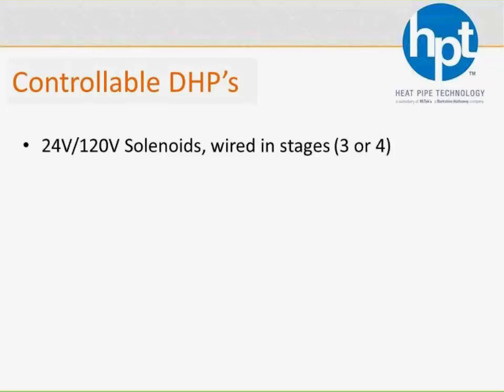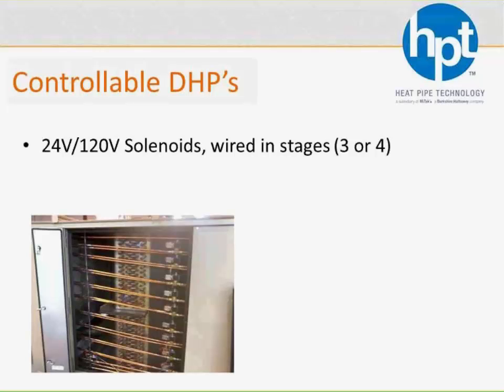You put control valves on the heat pipe. So typically we're going to use 24-volt solenoid valves on the circuits. If we get a large number of circuits, we'll bump that up to 120 volts to keep everything a little bit smaller. And then we stage those valves together, typically 3 or 4 stages, so you get 3 or 4 stages of heat pipe control. And here's one showing for you. So let's say there's 12 solenoid valves there. We wouldn't take the top 3 and make that a single stage, because if you turn that off, now you have warm, humid air coming through the top of the coil and conditioned air coming through the bottom, and that's no good. You don't want to have any stratification like that. So we would actually stagger, let's say there's 4 stages, every 4th valve to be 1 stage, so you're getting a nice consistent temperature gradient coming to your cooling coil.